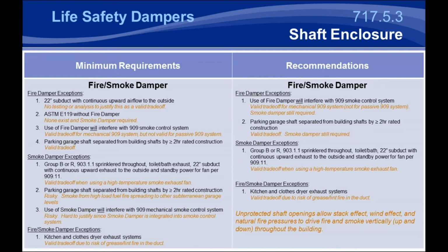One valid trade-off we always recommend is for kitchen and clothes dryer exhaust systems. Now, the Uniform Mechanical Code does not allow for dampers in these systems, but the International Building Code allows the trade-off to remove the fire and smoke dampers in shafts when used for kitchen and clothes dryer exhaust, and that is incredibly valid. Any damper or anything in that ductwork will collect grease or lint and create a fuel load that could then ignite in that shaft, and because of that, you really don't want to have any fire damper or fire smoke damper in these types of exhaust systems.